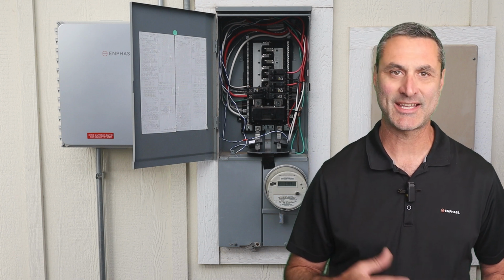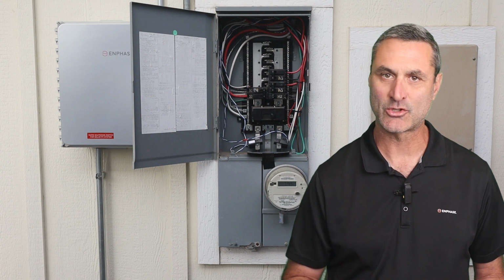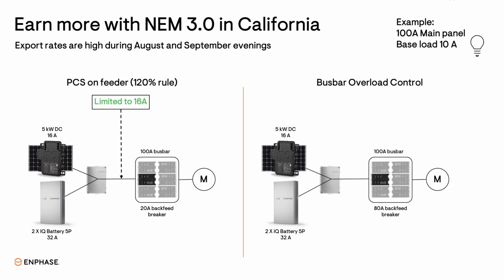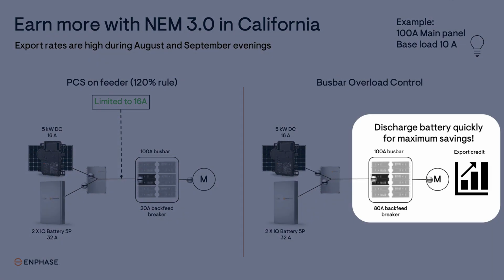They can save more money by sending more battery energy to the grid and earning larger bill credits. With the NEM 3.0 tariff, there are specific times of the year, namely August and September evenings, when the price the utility pays for energy is significantly higher than the retail price. At these times, it's beneficial to export battery power to the grid to earn credits. Usually these windows of opportunity are only 1 or 2 hours. With busbar overload control, the IQ Battery 5P power output won't be restricted, and it can discharge all of its energy in only an hour and 20 minutes, making the most of these short periods with high export rates.